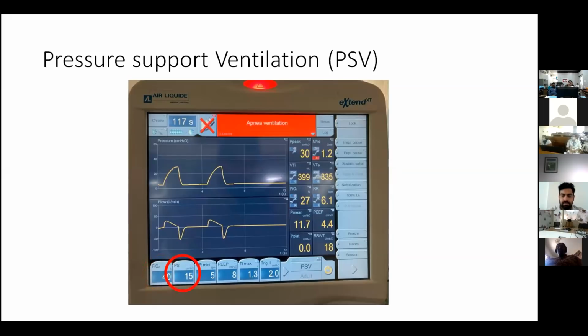We keep pressure support which is above PEEP, and the target of the pressure support is to deliver a tidal volume of 6 to 8 ml per kg of predicted body weight. This is the minimum respiration rate, so it is the backup setting. If the respiration falls below a particular range, maybe you have given some sedation, some paralysis, something went wrong, then it is the backup so that the patient may not die because of hypoxia.